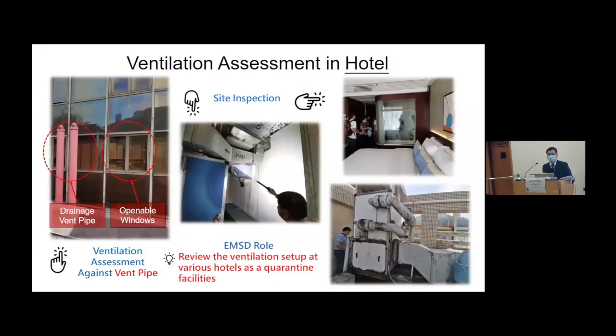Apart from the airflow pattern, we will also check the distances between fresh air intake and sources of pollutants, such as exhaust air outlets and drainage vent pipe outlets, to ensure no foul air will be short-circuited or infiltrated into fresh air intakes. Although there is no recognized international standard on distance for hotels as inbound traveler holding facilities, we made reference to the requirement of 25 feet, which is approximately 7.5 meters, stipulated in the ASHRAE standard, as well as the CDC's guidelines for environmental infection control in healthcare facilities.